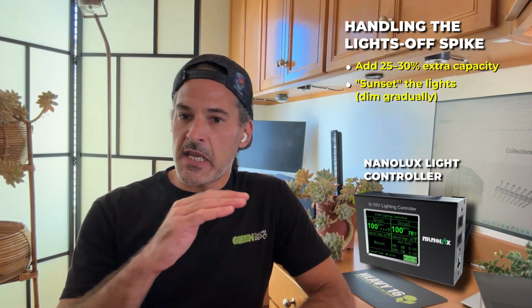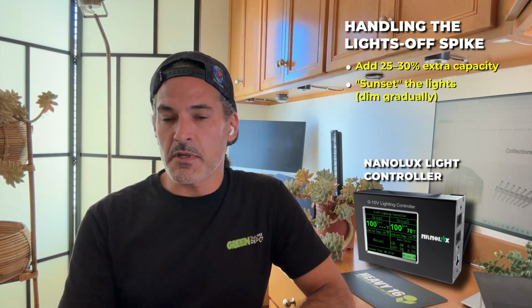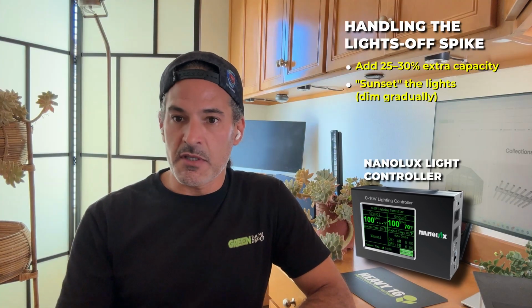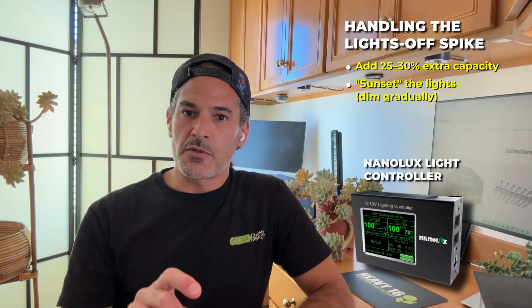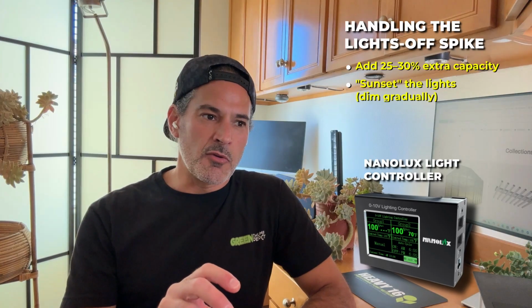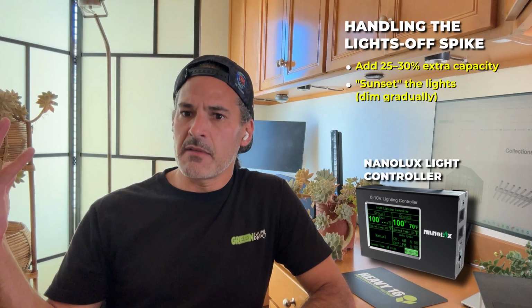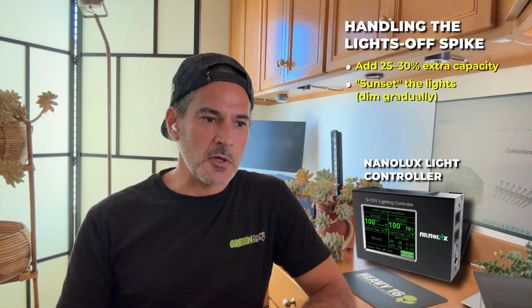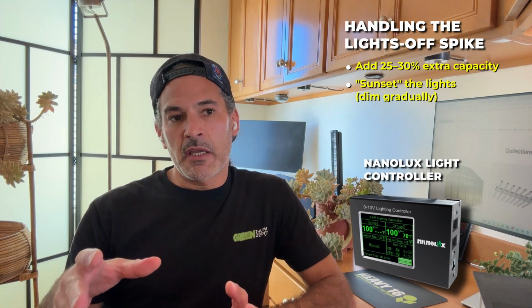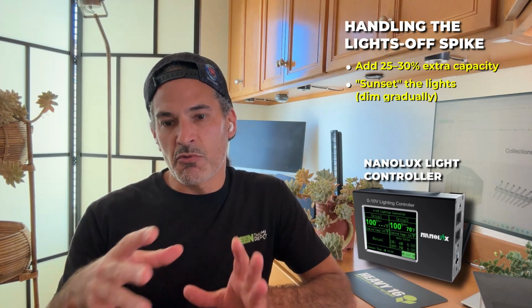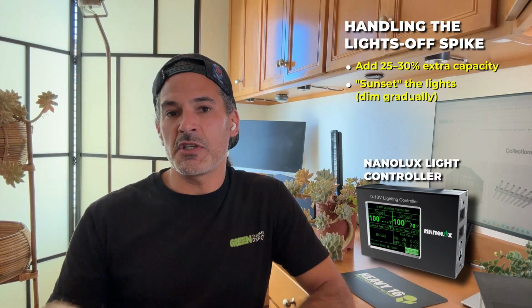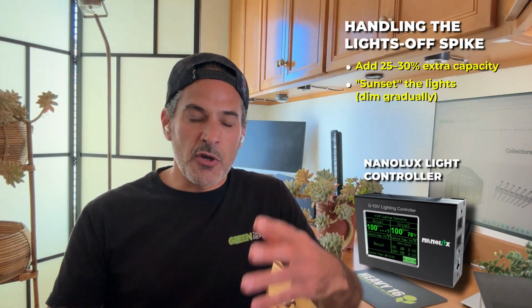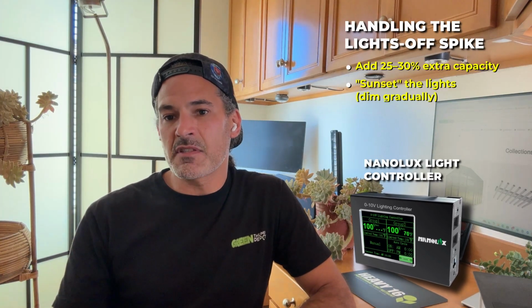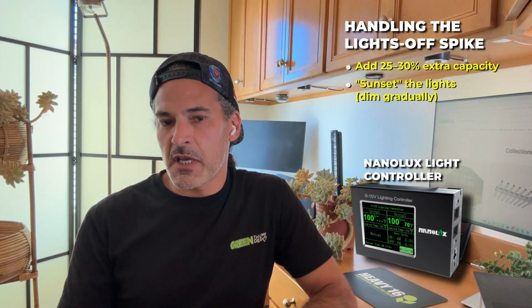Absolutely. One of them is to do what we call sunsetting the lights. So instead of just taking it from full blast at 100% light output and then going to zero, we can use our light controllers to gradually dim the lights over maybe the last half hour, kind of simulating natural daylight and how the sun works. By doing that, you're allowing the conditions in the room to gradually accommodate these changes. The humidity and the temperature will all start changing slowly, and that gives time for the dehumidifiers to actually catch up.